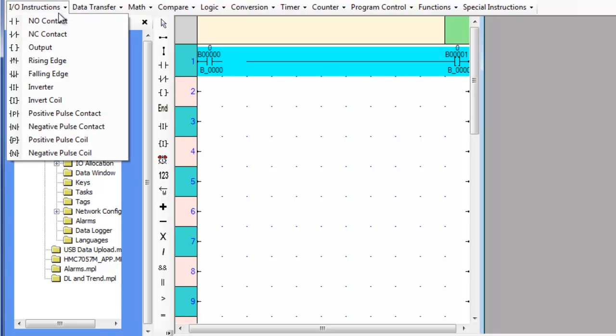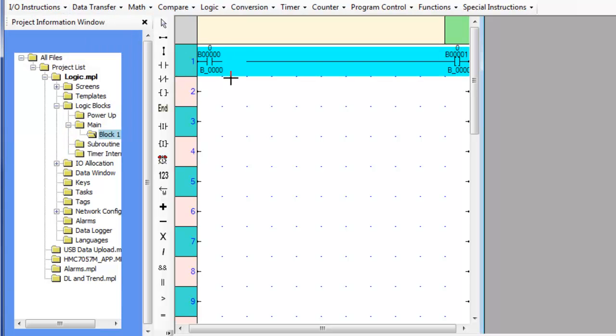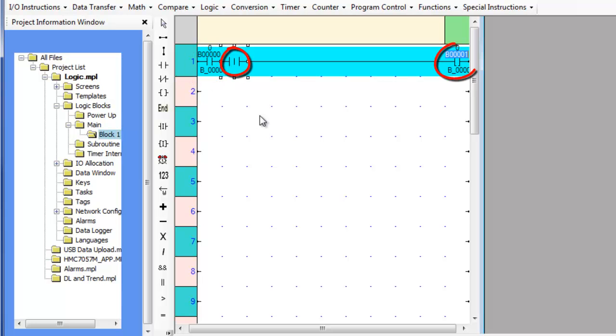The inverter transitional contact is a function that will invert the state of the conditions preceding the inverter. If bit B0 is off, causing the normally open contact to be opened, the inverter will make the following rung condition true. The execution time for this instruction is 0.8 microseconds.